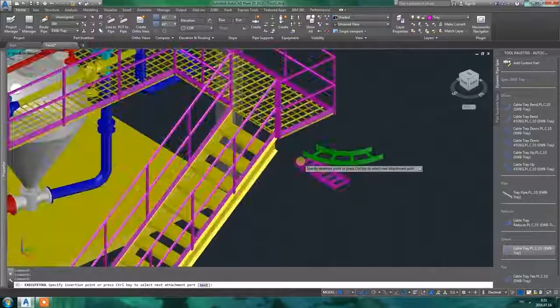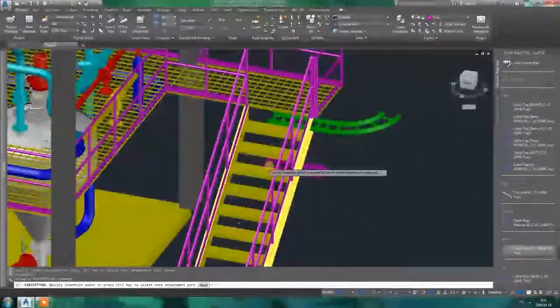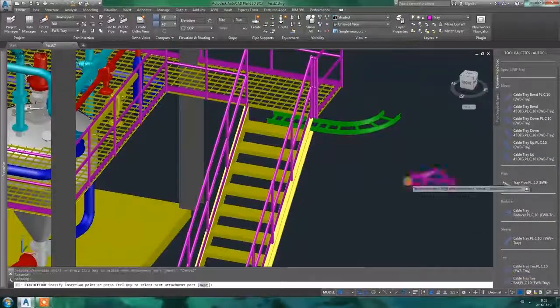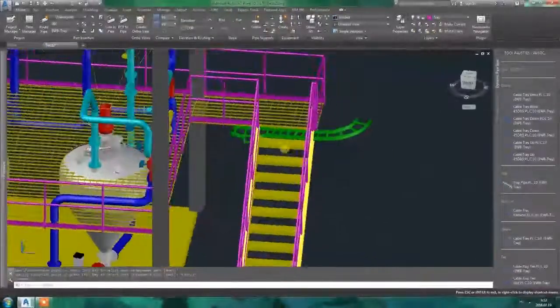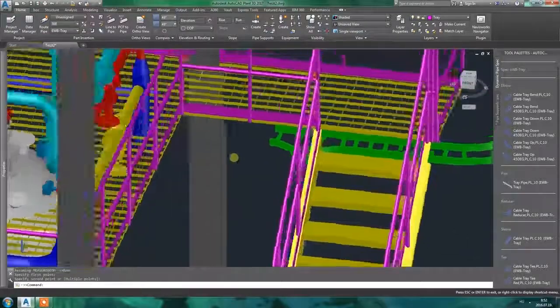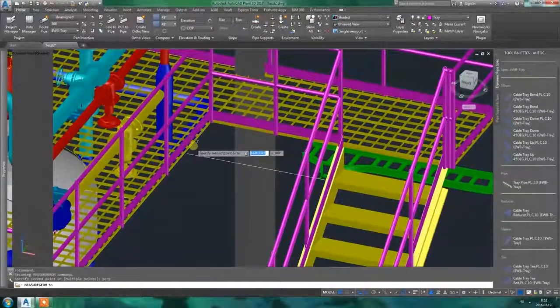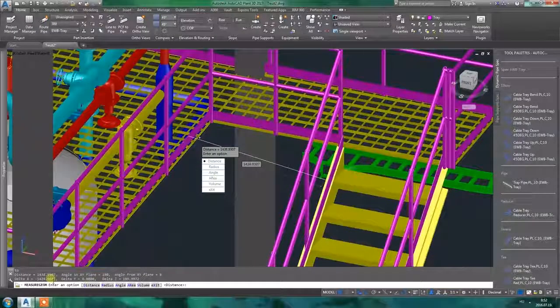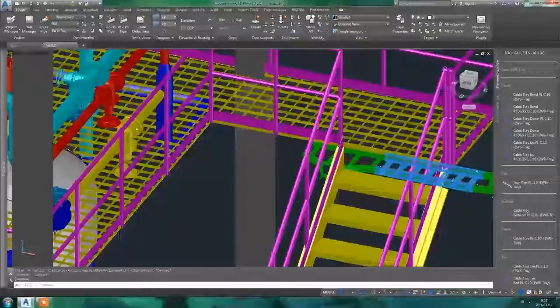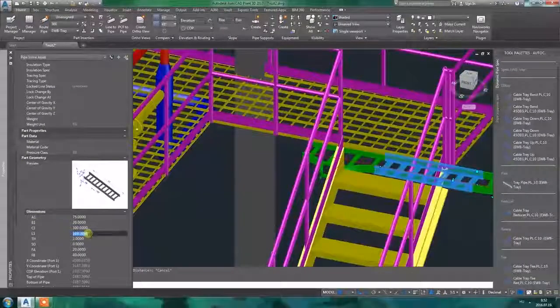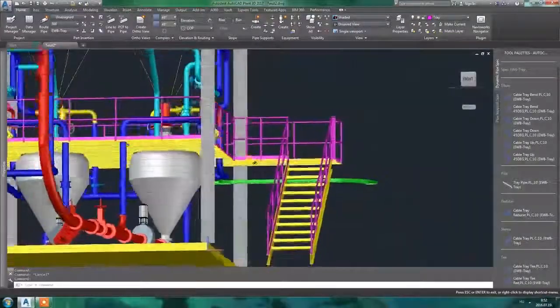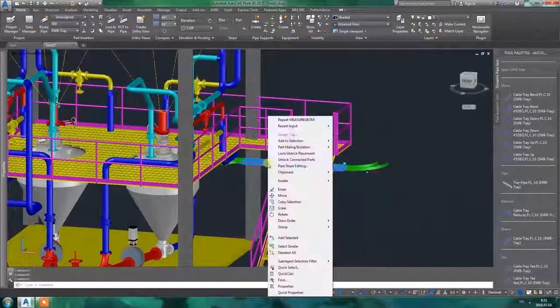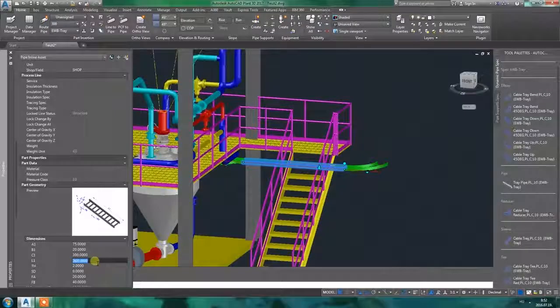Let's start with a straight section first. We are putting it as a sleeve. And now I am putting a reducing T. Of course this T is not in a good position now. I will check the distance from this railing. I would like to go below it. So I need at least 1400 millimeters. So this is the trick. The sleeve is editable. So if I extend the length, it is working as a pipe. We just have to edit the properties tab of this sleeve.